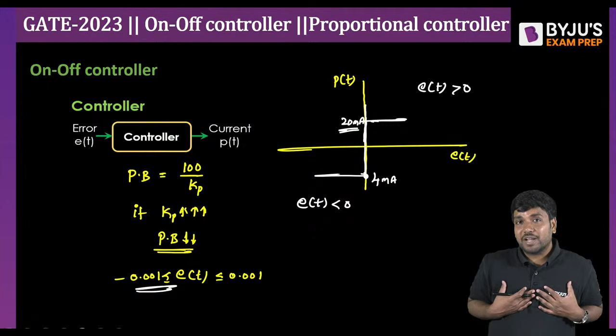For a very small error, it will take aggressive action. If the error is slightly negative, you will get 4 milliampere, an immediate extreme output. If the error is slightly positive, you will get 20 milliampere. So is it good or bad? It is so aggressive, right? We don't really require this. If you put this on-off controller in the previous case, what happens here? 0.9 meter to 1.1 meter we will continuously toggle, right?